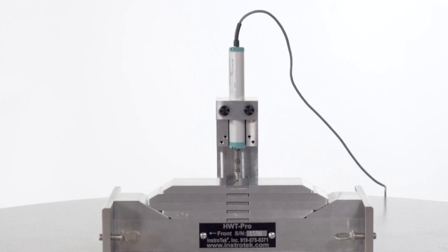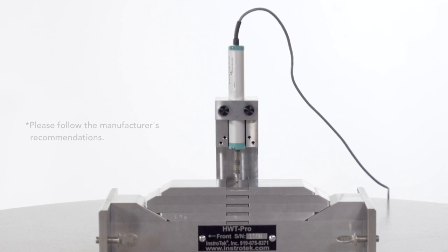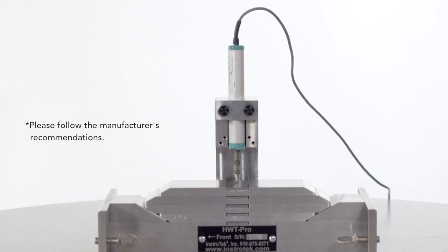The HWT Pro displacement calibrator is an optional jig used to calibrate the Hamburg's LVDT and height sensors. A simple calibration process adjusts the linearity of the LVDT and assures accurate rut depth measurement.